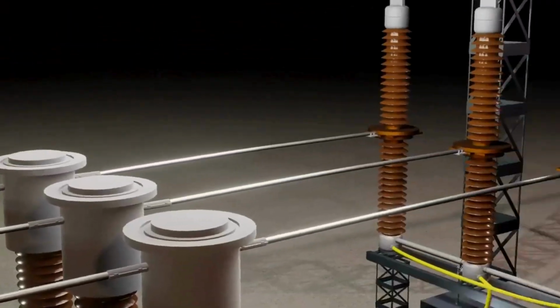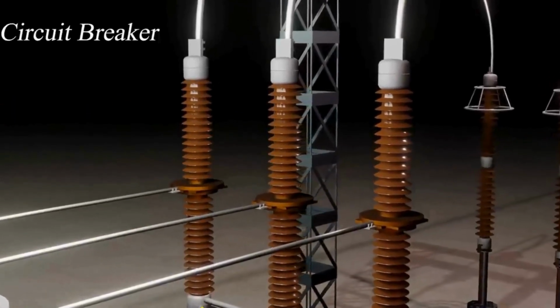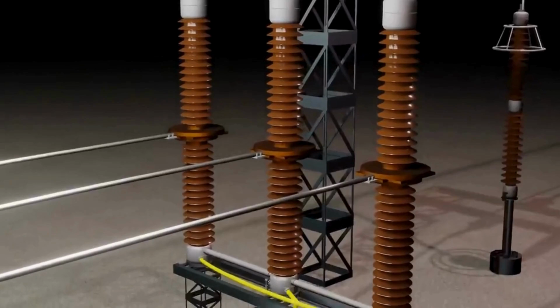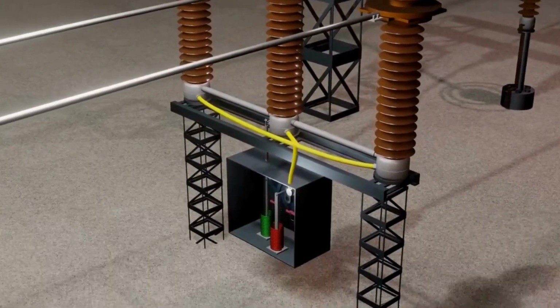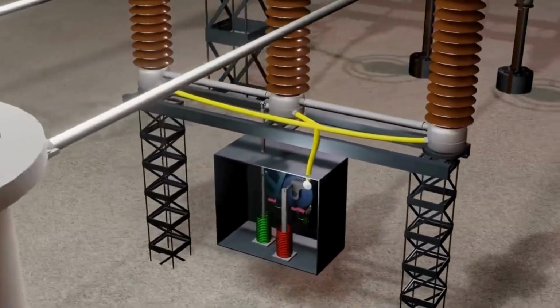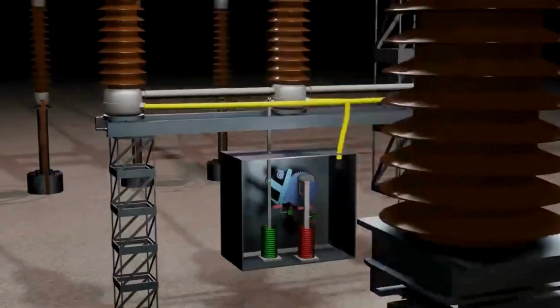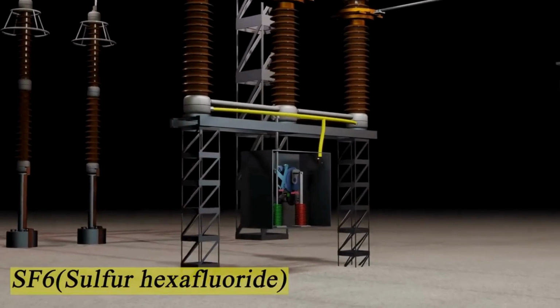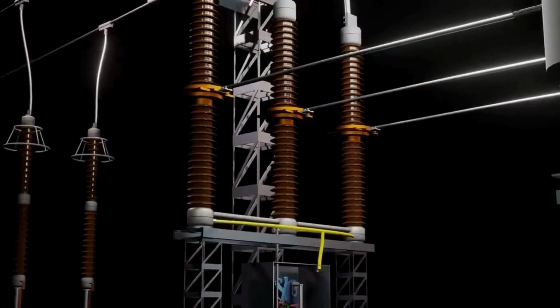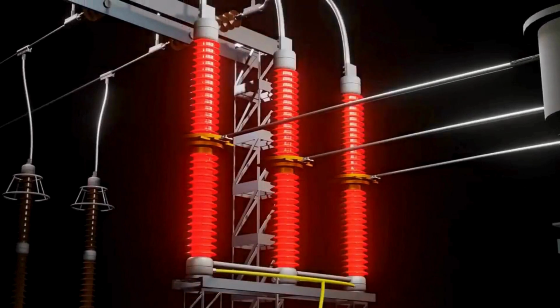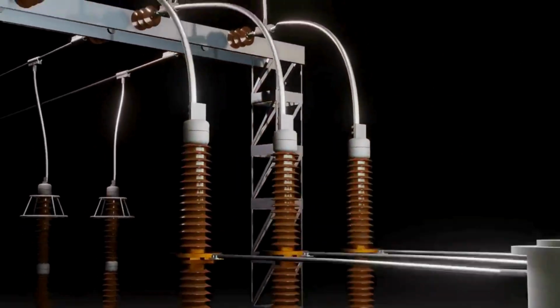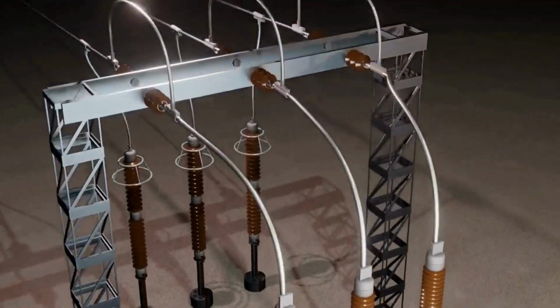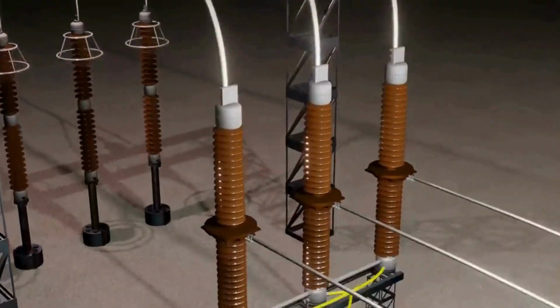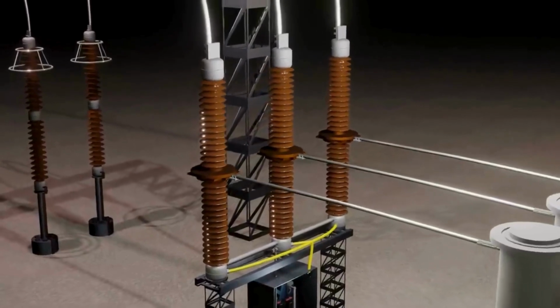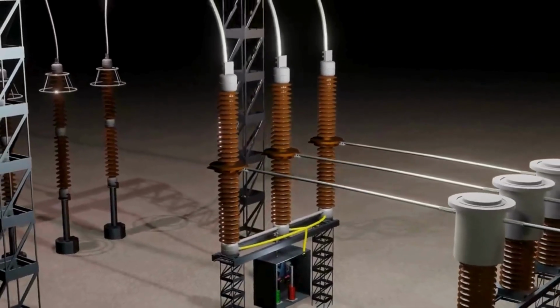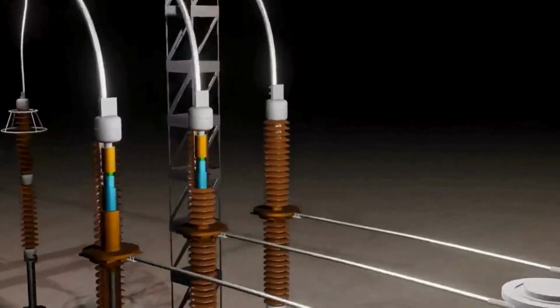So a powerful device was made to break the line, which is called a circuit breaker. It can break any line from 132 kV to 1100 kV with complete safety. And even if there is a fault in the line, it trips automatically. The circuit breaker you are seeing has the same mechanism for all three phases, but this mechanism operates in different bushings. The upper terminal comes from the main line, and the output of the circuit breaker comes out of the lower terminal. Now the mechanism to break the circuit is installed in between these two terminals.